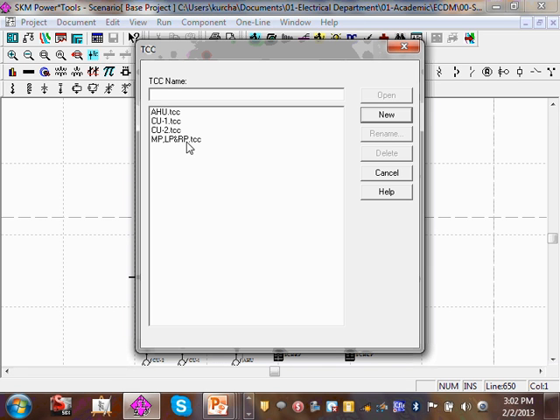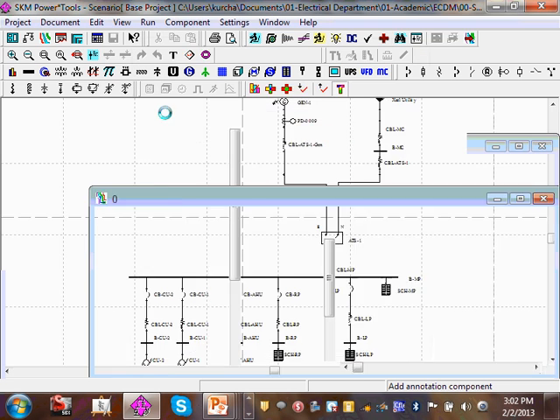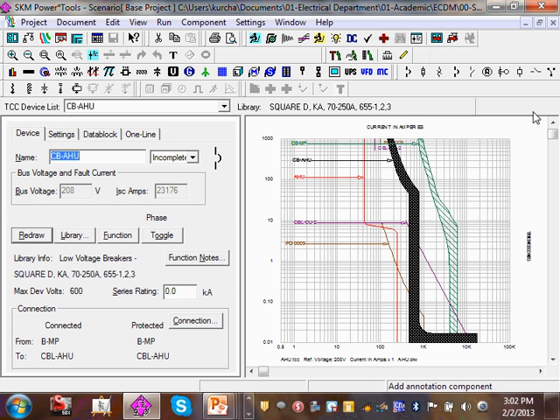Let's go to main panel air handling units right here. If you look at this, you get these beautiful fancy circuit breakers. The first circuit breaker, guys, right here, this is circuit breaker MP. That's the main circuit breaker for the panel. Can you guys see that green one? The second, the black one here, is the circuit breaker that protects the air handling unit. That brown wire here is the starting curve of the air handling unit. So when you flip the switch on the air handling unit or push the button, the air handling unit is going to have an inrush, right? From this value here, it's going to go up, up, up, up, almost 10 seconds.